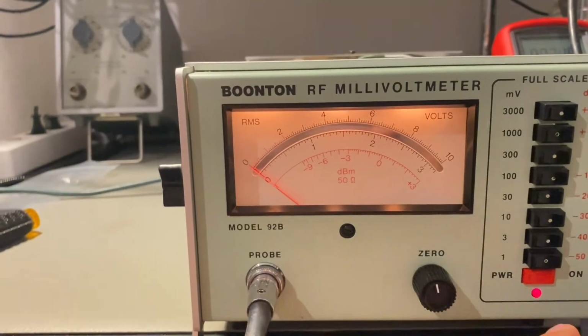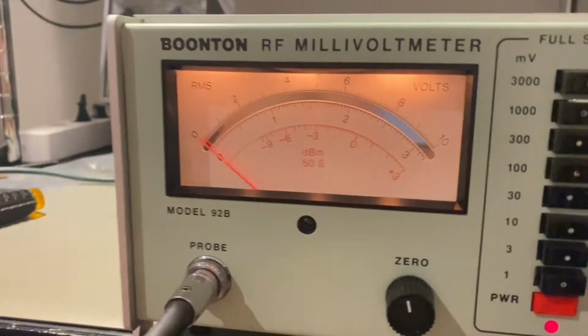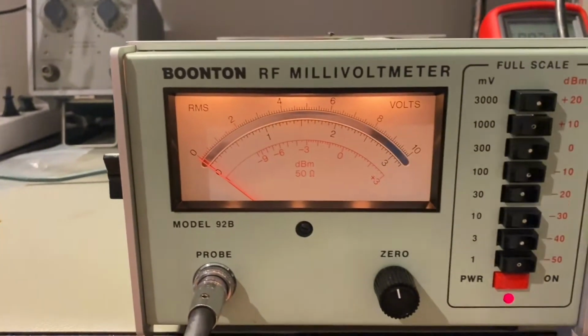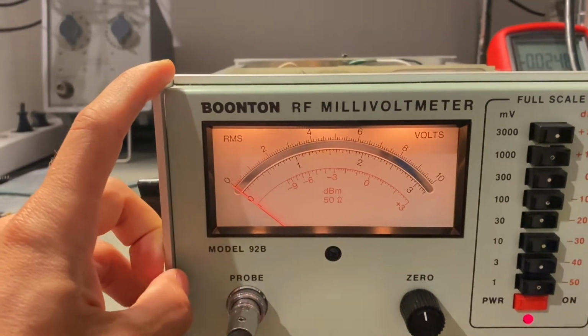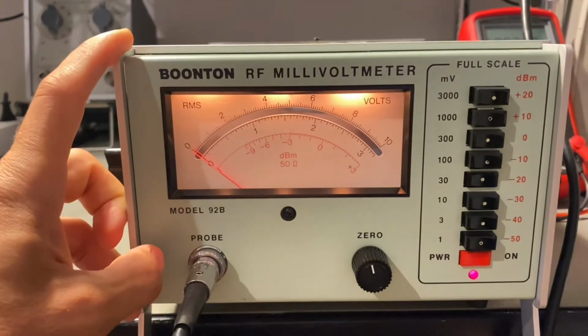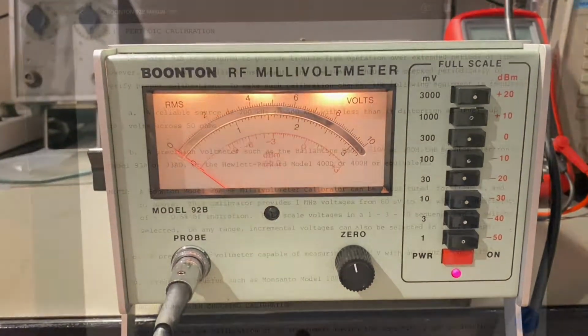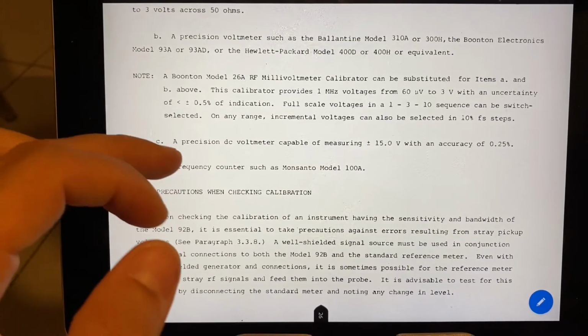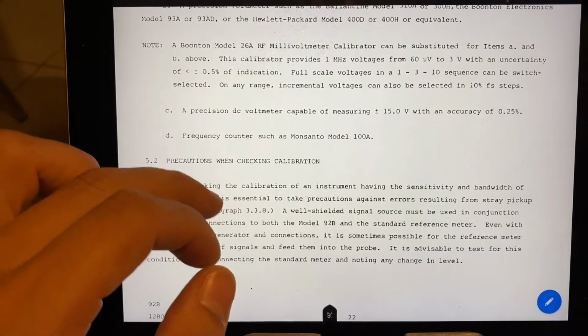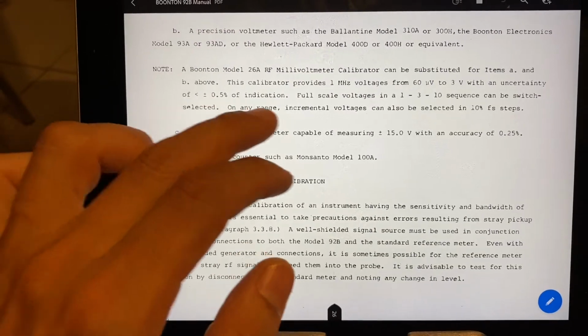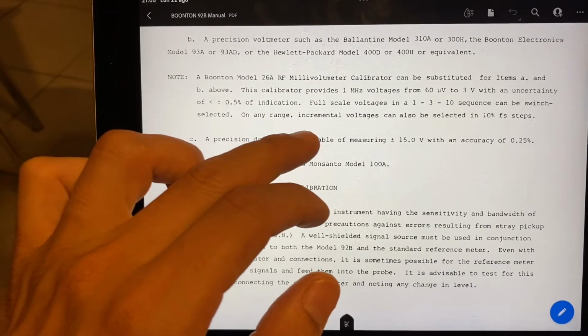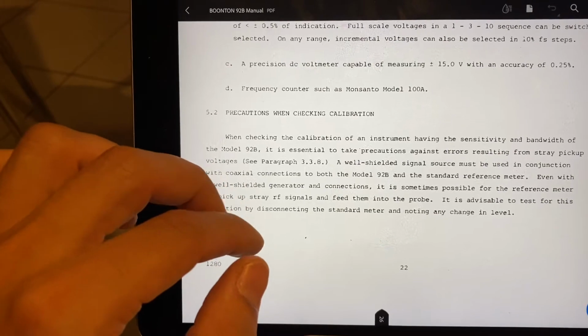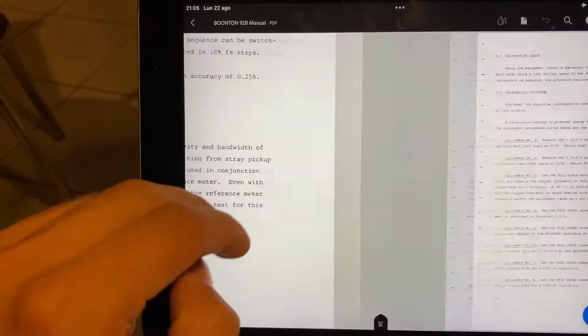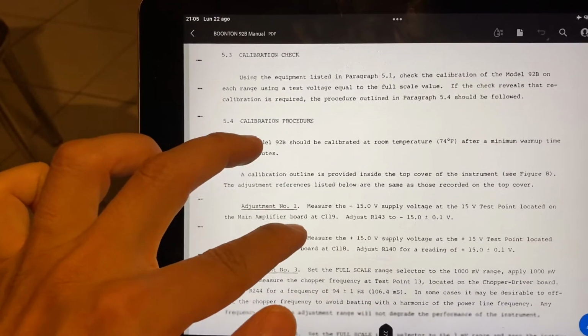Anyway, I want to recheck. This was calibrated by me before, but it looks like now it is a bit off. I want to recheck the calibration, so we'll go through that now. There are some conditions to follow for the calibration. Those are all stated here in the manual. One is, for example, the room temperature and the 5 minutes time on. Now it's been on for a while, so no problem there. So let's jump through the first steps.